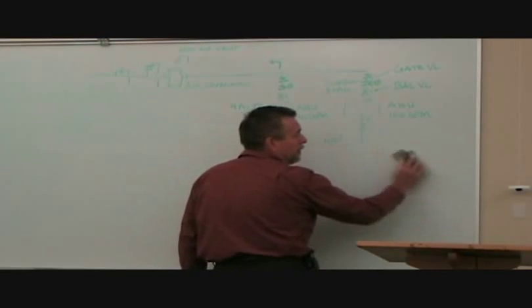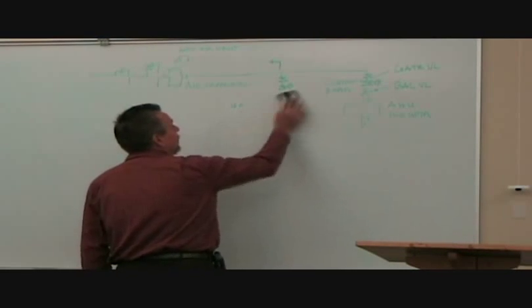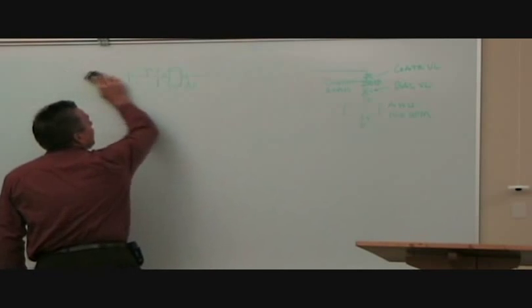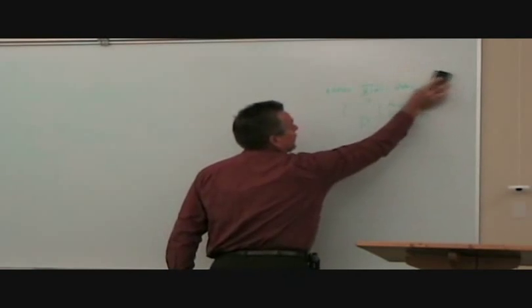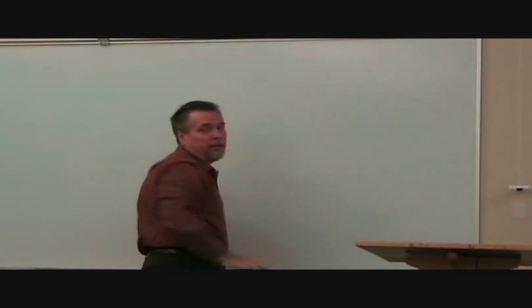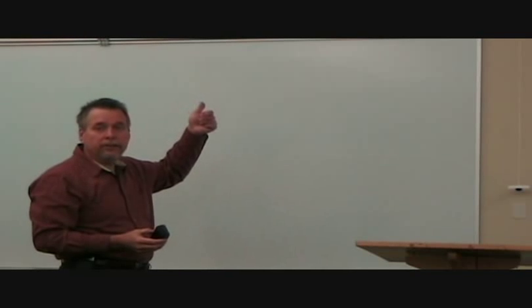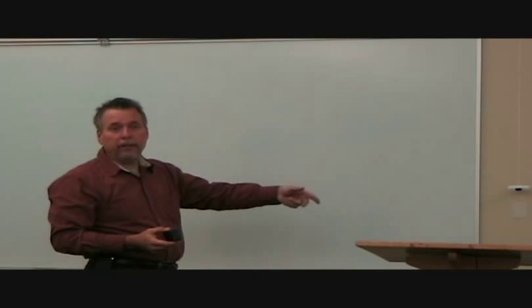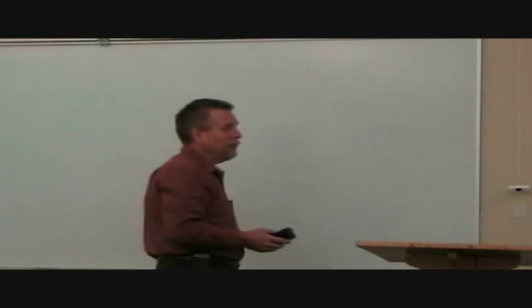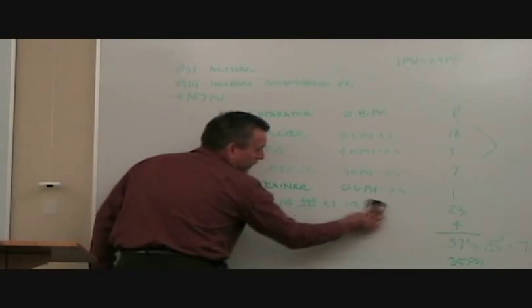But we selected the closed loop system at something less than 6 feet per 100, maybe a reasonable pressure drop per 100 feet of pipe. And on a cooling tower suction, when we go through this net positive suction head calculation, you'll see you don't want any pressure loss. So that pump suction from the cooling tower may actually be larger than your discharge pipe, because I didn't want any pressure loss in that pipe. So you might see an 8-inch suction and a 6-inch discharge on a pump for a cooling tower on occasion. Not very often, but it depends on, again, how far that cooling tower is away from the pump.